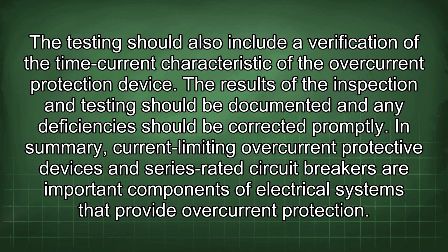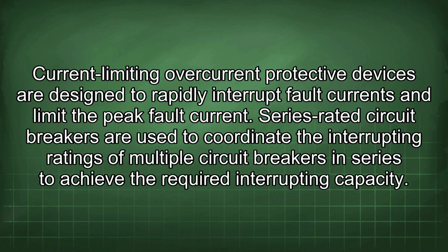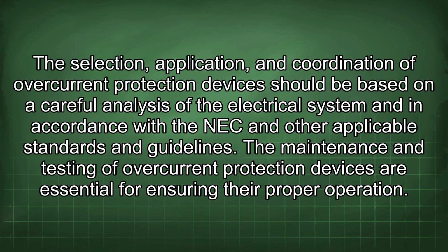In summary, current-limiting overcurrent protective devices and series-rated circuit breakers are important components of electrical systems that provide overcurrent protection. Current-limiting overcurrent protective devices are designed to rapidly interrupt fault currents and limit the peak fault current. Series-rated circuit breakers are used to coordinate the interrupting ratings of multiple circuit breakers in series to achieve the required interrupting capacity. The selection, application, and coordination of overcurrent protection devices should be based on a careful analysis of the electrical system and in accordance with the NEC and other applicable standards and guidelines.